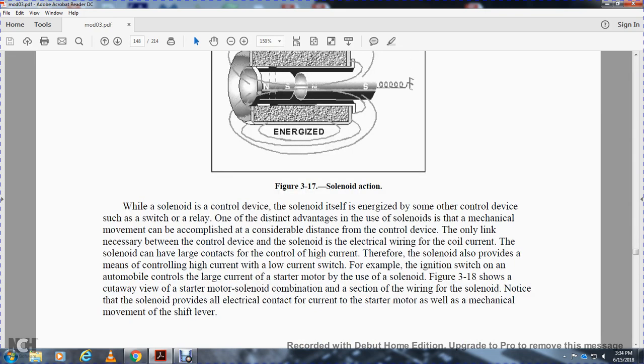Well, the solenoid is a control device. The solenoid itself is energized by some other control device, such as a switch or relay. Another distinct advantage of using a solenoid is that the mechanical movement is accomplished at a considerable distance from the control device. Only wiring is necessary between the control device and the solenoid for the current to the coil. The solenoid can have large contacts to control high current. Therefore, the solenoid provides a means of controlling high current with a low current switch.